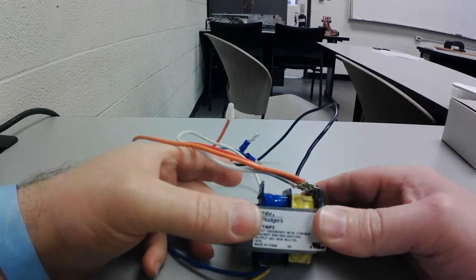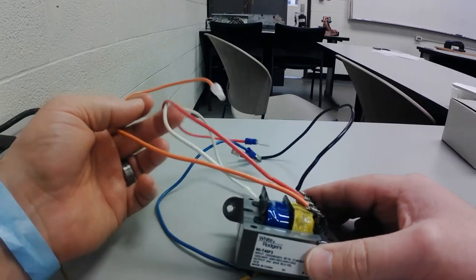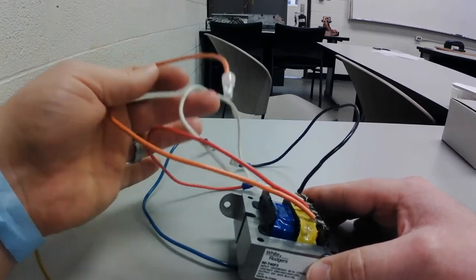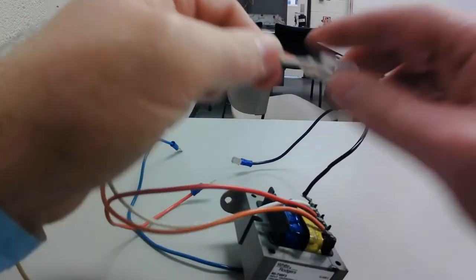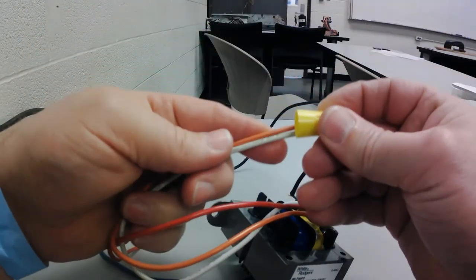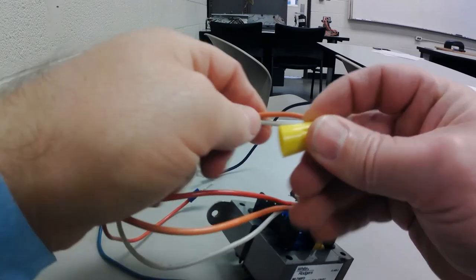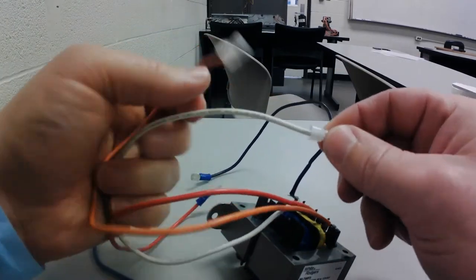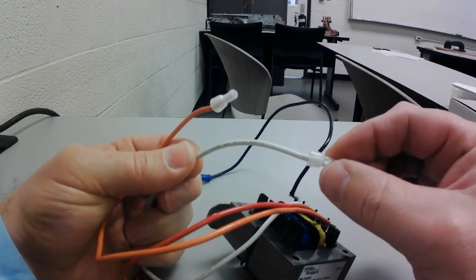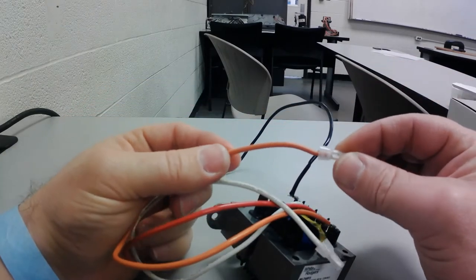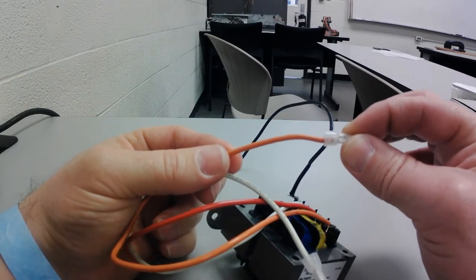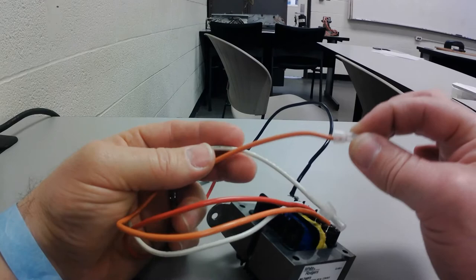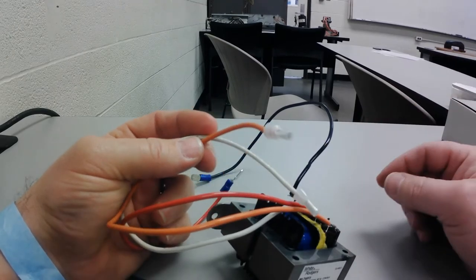There's been a couple technicians out in the field. They'll take the unused terminals, and what they'll do is they'll try to put them in a wire nut together, and you don't do that. What you want to do is individually cap each of the wires, because even though they're not used, they have voltage on them when power's to the unit. And I'm going to show you that here in just a minute.